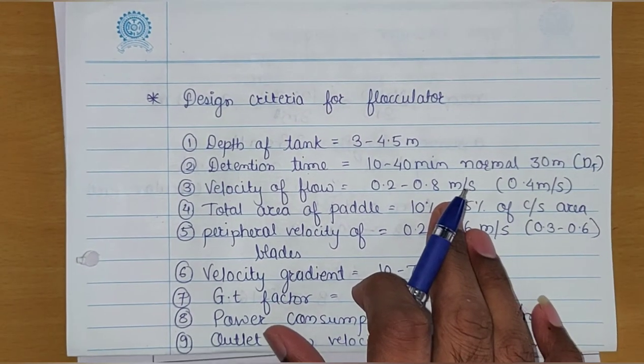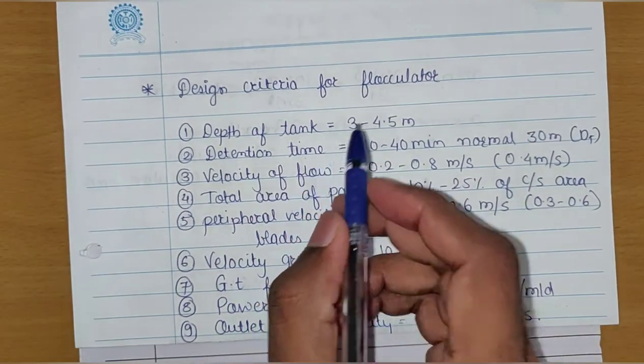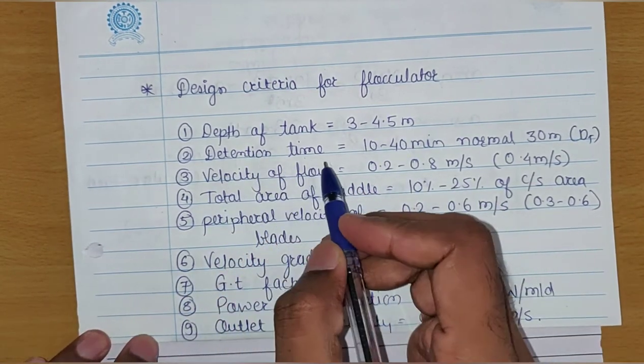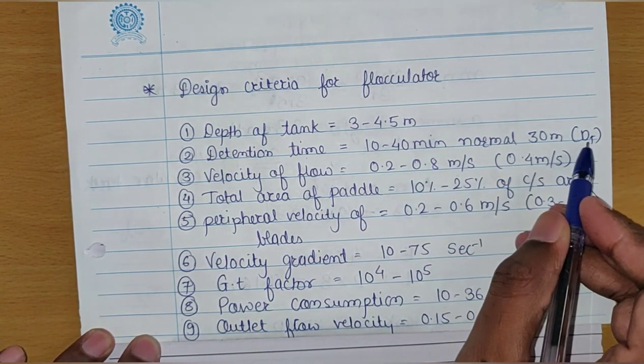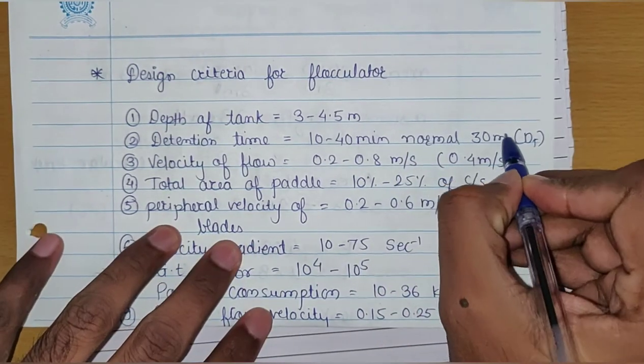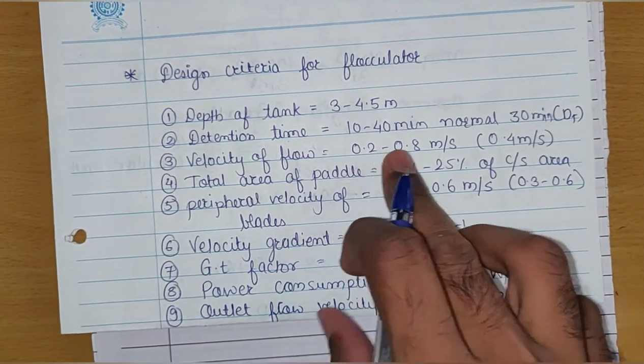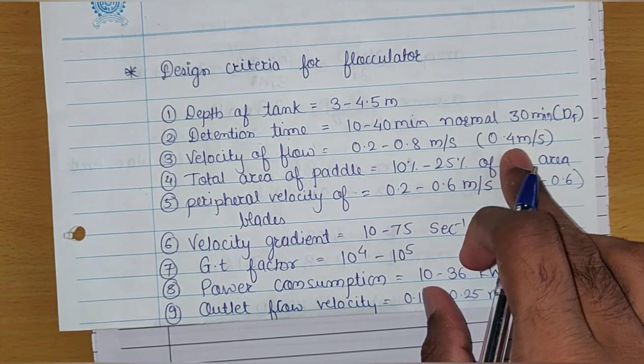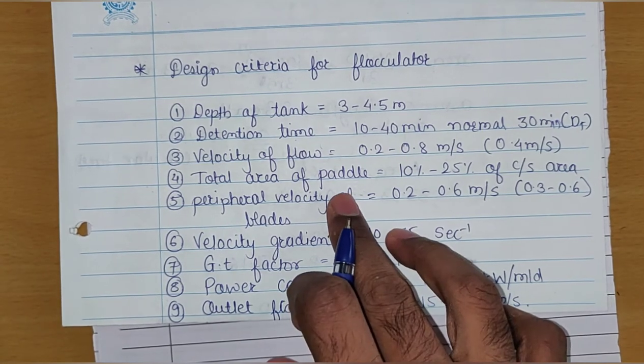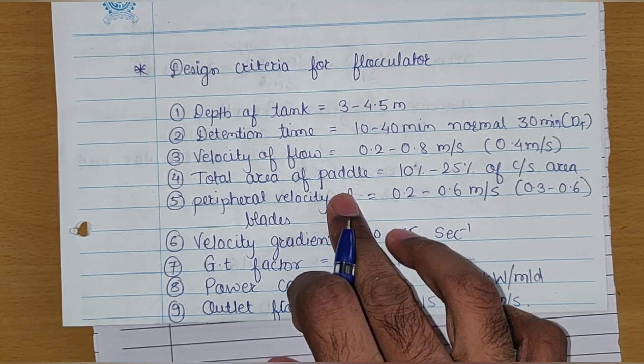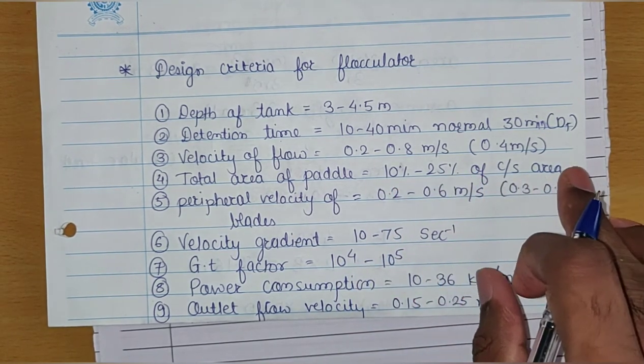First we will see the design criteria for the mechanical flocculator. The depth of the tank should be between 3 to 4.5 meter. The retention time for the flocculator is between 10 to 40 minutes, with 30 minutes normally taken. The horizontal velocity of flow is between 0.2 to 0.8 meter per second, preferably 0.4 meter per second. The total area of the paddle should be in the range of 10 to 25 percent of the cross sectional area.